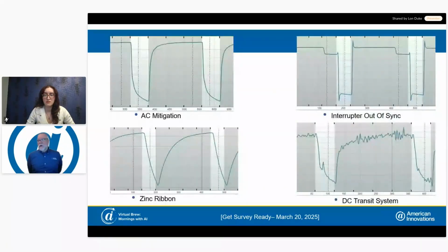Now you can see a whole range of issues out there. Any type of AC mitigation, again, I said this before, it wreaks havoc on an interrupted survey. You get this capacitive discharge and recharge. Now for this particular case, it's really up to you what you're going to do with that. Dairyland now has a PCRX that takes care of this. It clears this up. You get a good square wave with the PCRX now. It's a really nice PCR that they put out there.